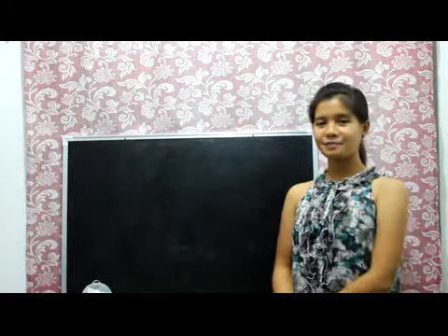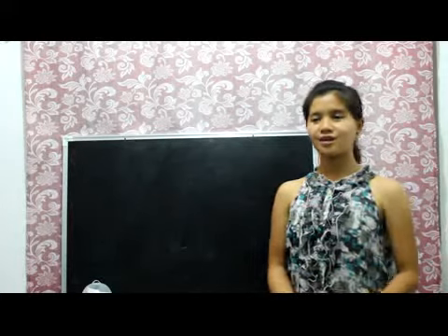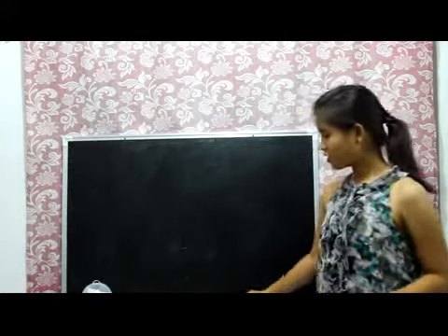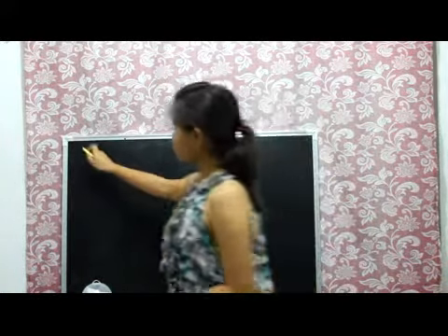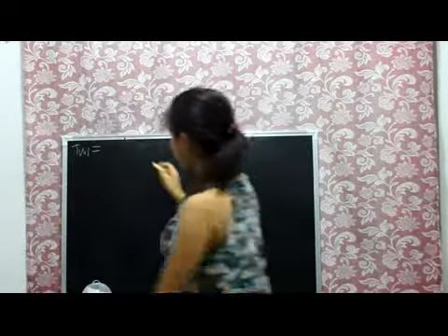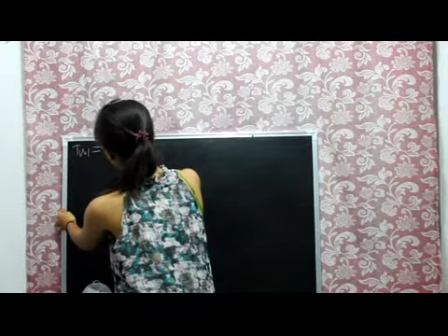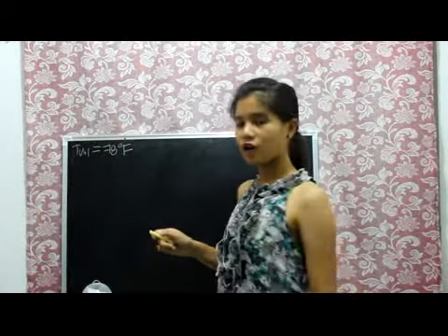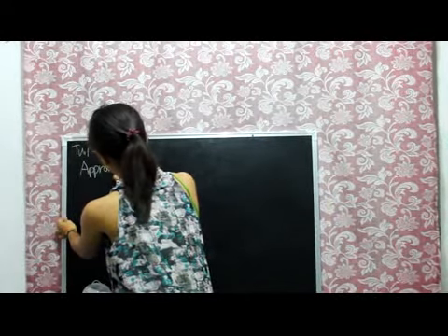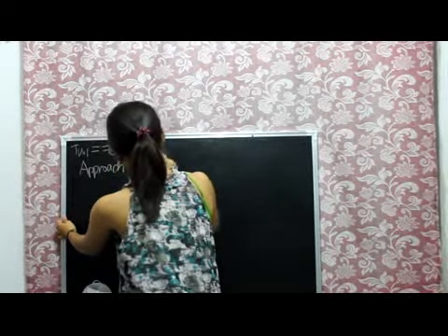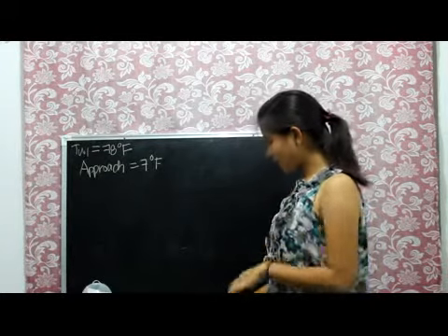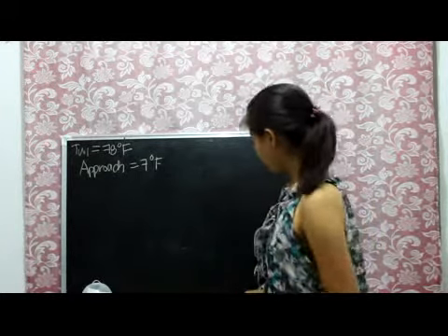So let's now proceed to the last part of sample problem number 1. We are asked here how much more of the fill is needed if you're given a different wet bulb temperature that is equal to 78 degrees Fahrenheit and a value of the approach that is equal to 7 degrees Fahrenheit. So from this given, we can get the value of HV1.